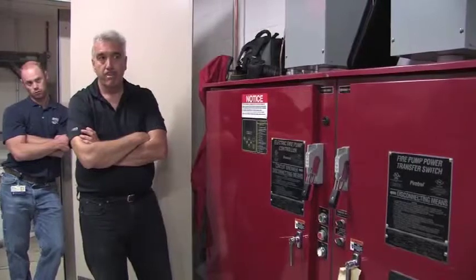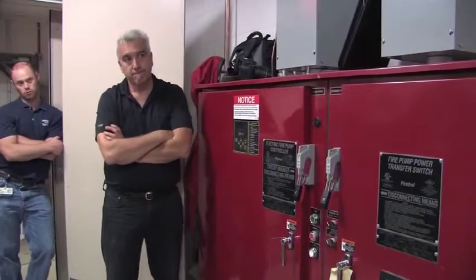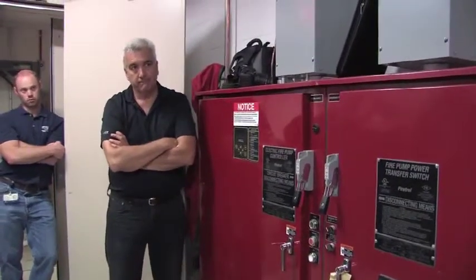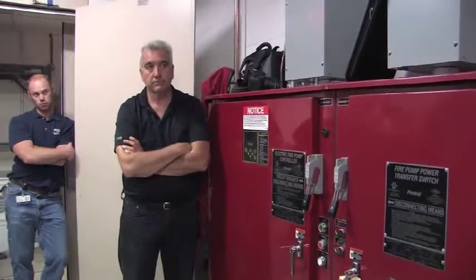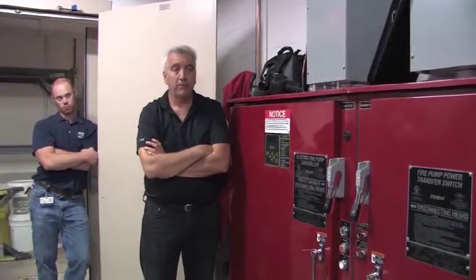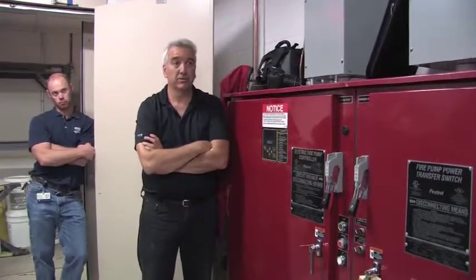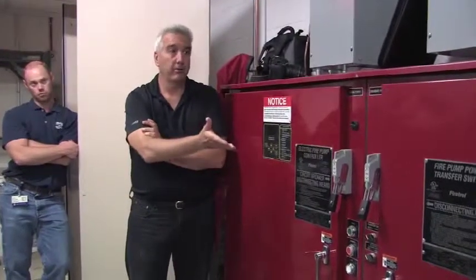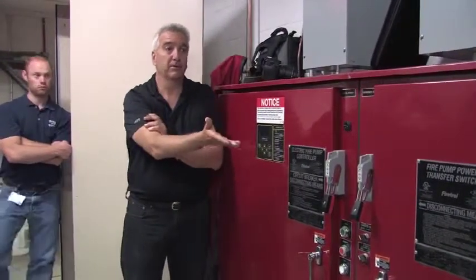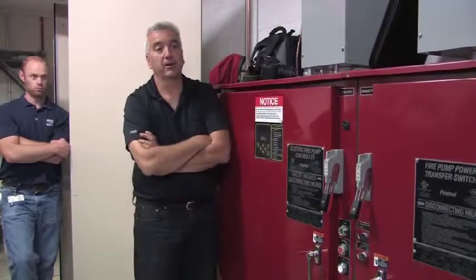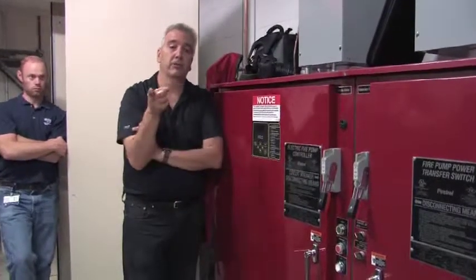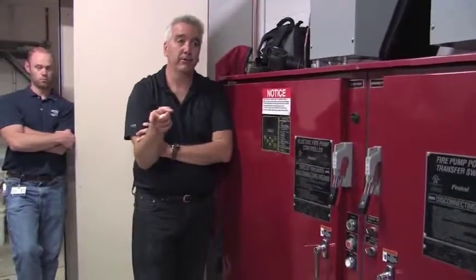That's something, you brought up a good point, that's what they're going to want to see. What's that? Proper testing sequence for all the pumps and the controls. Mm-hmm. Yeah. Well, every building's a little bit different depending upon the hydraulics of the building. So exactly. Brian can't even tell you, because he hasn't been on campus and doesn't know all the buildings, but we can tell you what's very typical. We had a discussion about the pressure relief, the casing relief valve in the pump.